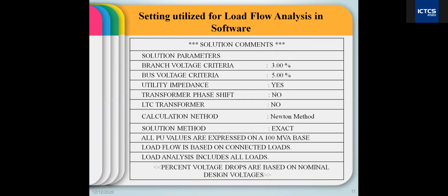Both loads I have considered here, and for this I have chosen some criteria. My criteria is that my branch voltage must be within 3%, my bus voltage criteria must be within 5%, and utility impedances utilized by the transformer and motor generator sets are considered. Transformer phase shift I have not considered. For this I have utilized the Newton-Raphson method. There are different methods of power flow calculation, such as the Gauss-Seidel method, Newton-Raphson method, and fast decoupled methods. I chose this because I require an exact solution.